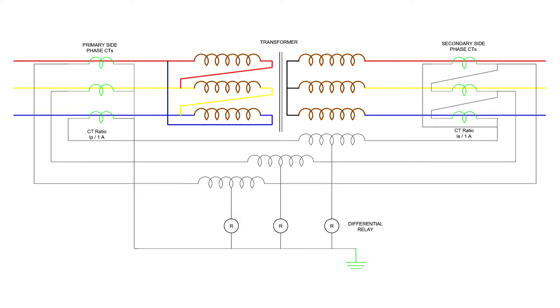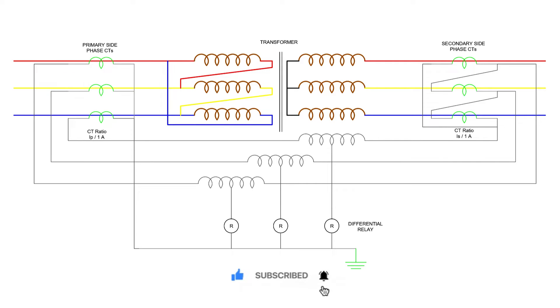But if any major fault occurs inside the transformer, due to which the normal ratio of the transformer is disturbed, then the secondary currents of both CTs will not remain the same. A resultant current will flow through the current coil of the differential relay, which will actuate the relay and inter-trip both the primary and secondary circuit breakers.